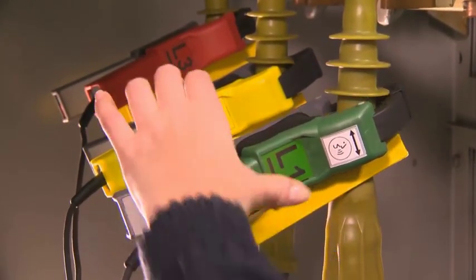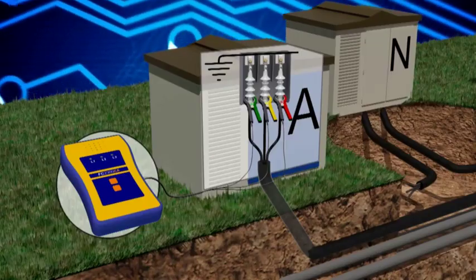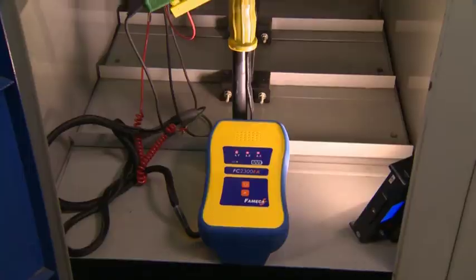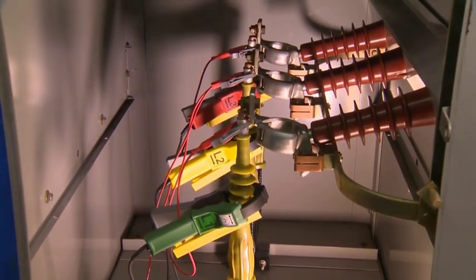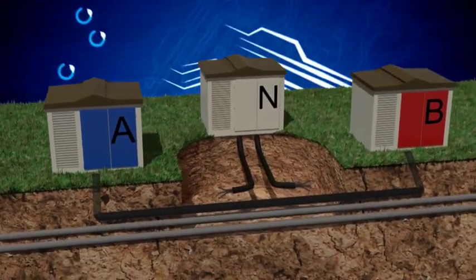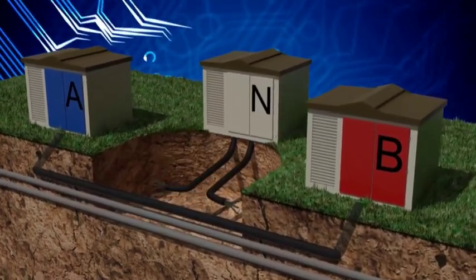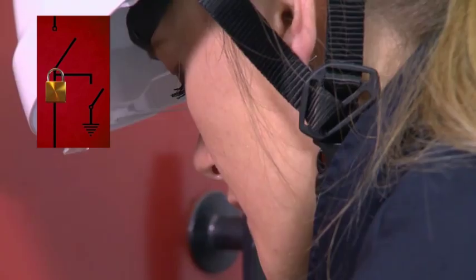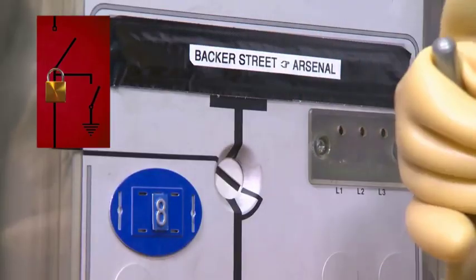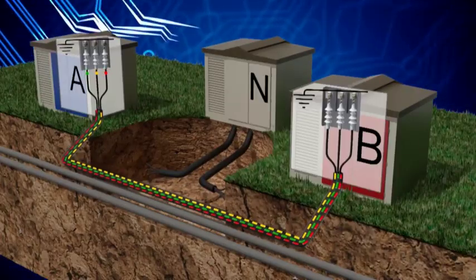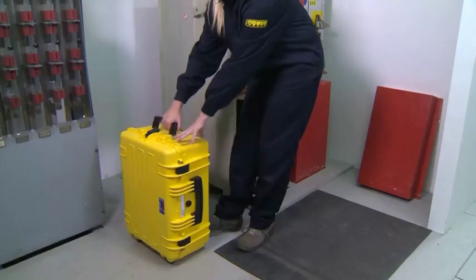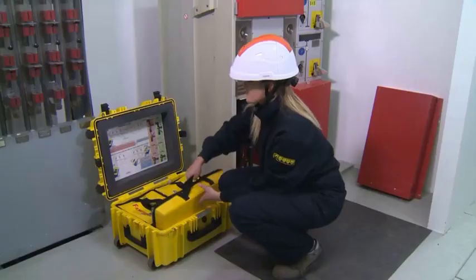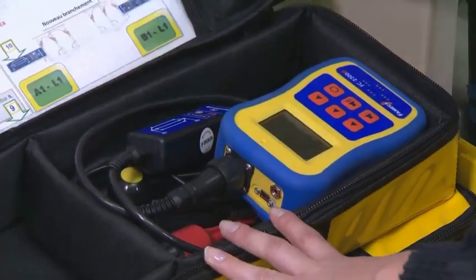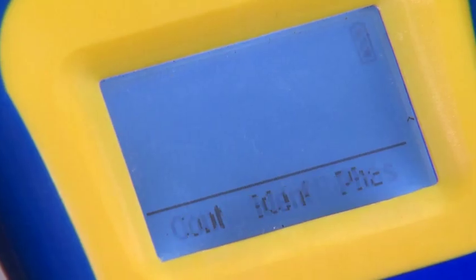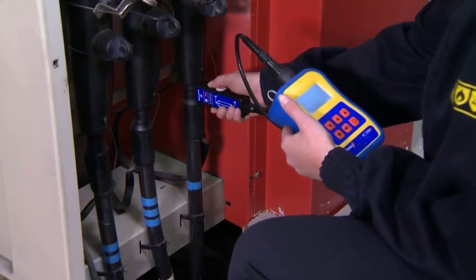Now the third clamp and the balancing shunt can be set up. Once the main transmitter is installed in substation A, go back to substation B to turn off the grounding switch and finalize cable grounding. The signal transmission circuit is established by closing the two grounding switches that short-circuit the cable terminals. Once they have been closed, we can check the continuity, which confirms, first of all, that we are on the right circuit and that the cable identification will be guaranteed on site. Continuity is checked by the clear identification of all three phases.